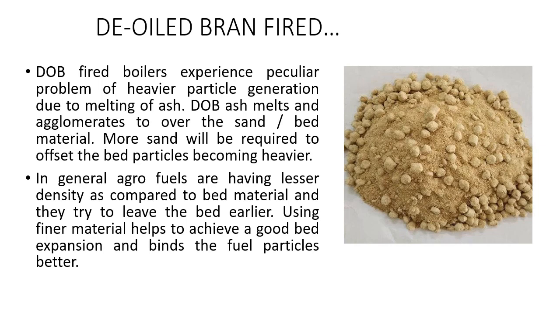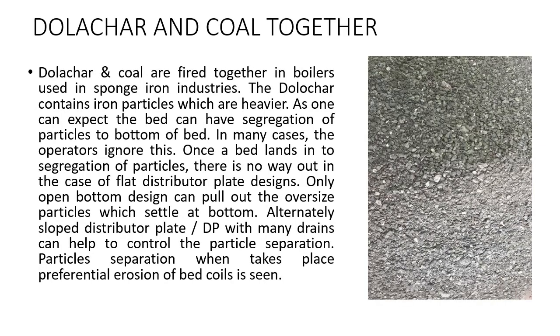Now the firing of dolachar and coal together. Dolachar and coal are fired together in boilers used in sponge iron industries. The dolachar contains iron particles which are heavier. As one can expect, the bed can have segregation of particles to the bottom of the bed. In many cases, the operators ignore this.